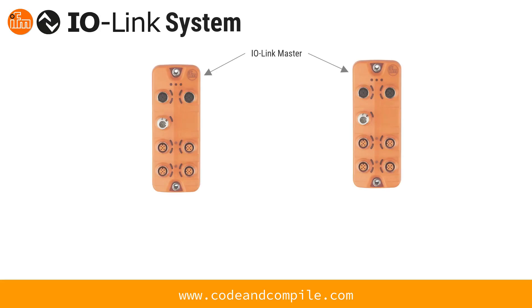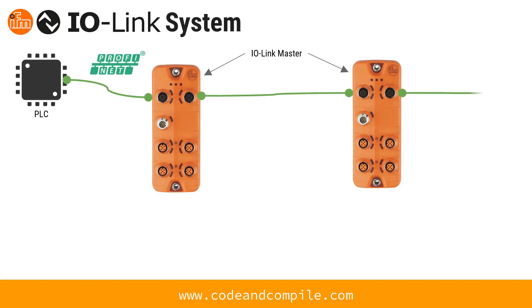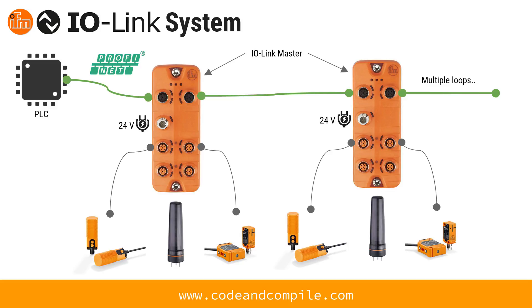Today we will look at the IO-Link master, which is the interface between your IO-Link sensors and actuators and the controller. The controller could be a PLC and the interface protocol is Profinet. This unit can be linked in series in multiple loops, is 24-volt actuated, and has four ports on the bottom for connecting sensors or actuators. Each port can be used for process values as an input or an output, but must be defined. This is the basic IO-Link system by IFM.